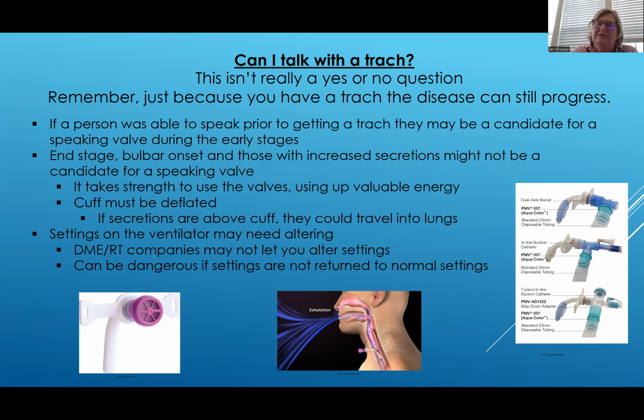If you go to the Passy-Muir site, they have classes you can take, including one about putting the valve in line with a ventilator. That class basically says you may need to change the settings on your ventilator because you have now added a leak to the system. So you have to include either more pressure or more volume to overcome the leak. I don't think you're going to find a respiratory therapy company that's going to let you manipulate settings on a ventilator. And what happens if you adjust the settings but forget to return them to normal afterward? That could be very dangerous.